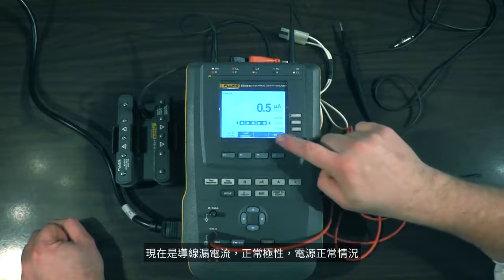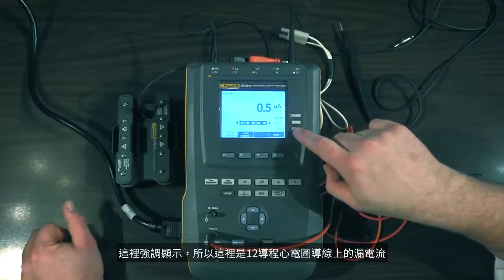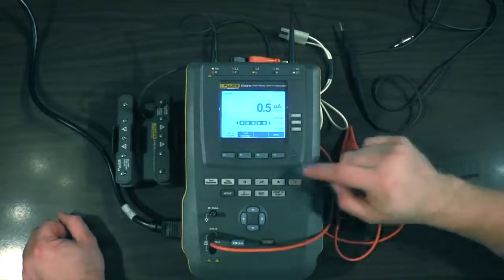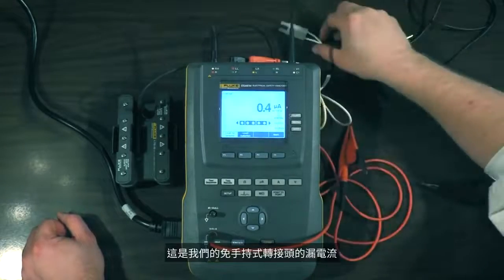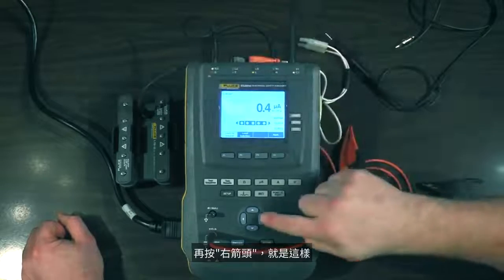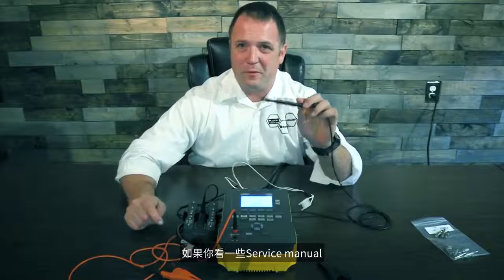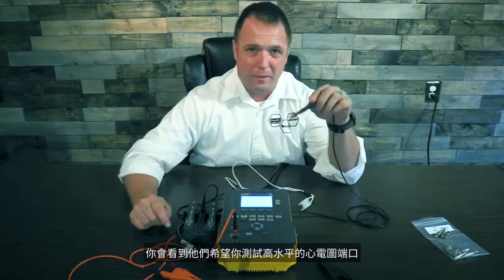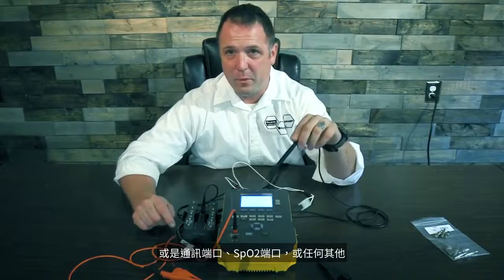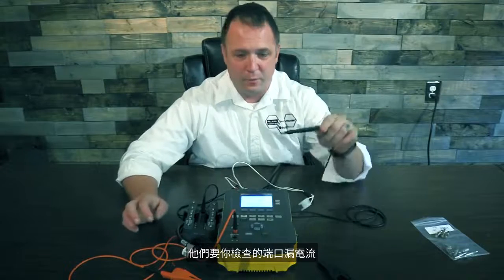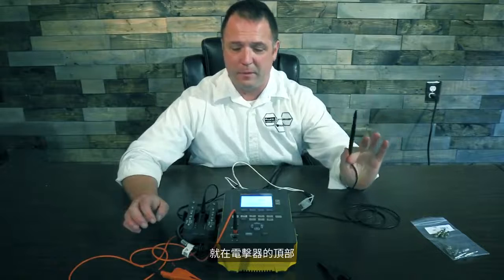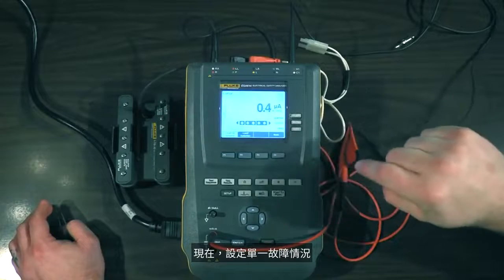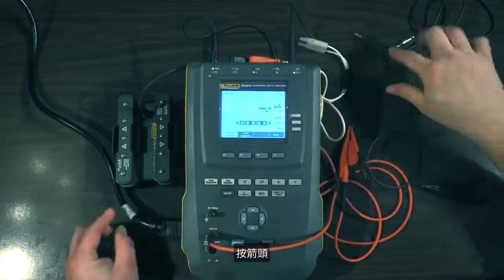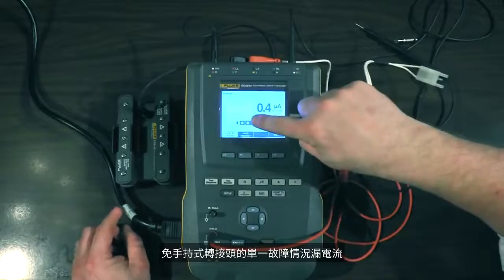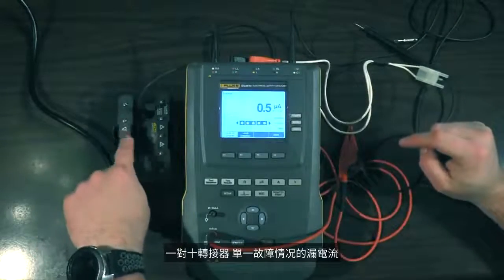Normal polarity, normal condition. This is highlighted, so here's the leakage on our 12-lead ECG. Over arrow, here's the leakage on our hands-free adapter. Over arrow. Now here we go. If you look at some of the service manuals, you see they want you to test the high-level ECG port, the COM port, the SpO2 port, any of these other ports they want you to check your leakage for. Right across the top of the defibrillator. Now, single fault condition, back across the top of the defibrillator. Over arrow, single fault condition for the hands-free adapter. Over arrow, single fault condition through the 1 to 10 adapter.